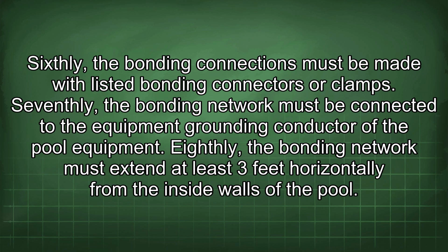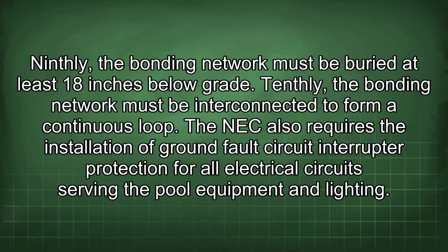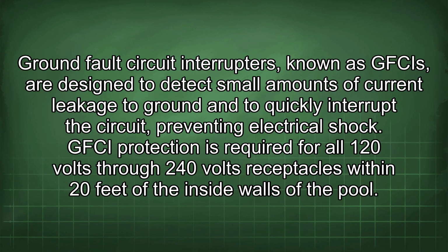Seventhly, the bonding network must be connected to the equipment grounding conductor of the pool equipment. Eighthly, the bonding network must extend at least 3 feet horizontally from the inside walls of the pool. Ninthly, the bonding network must be buried at least 18 inches below grade. Tenthly, the bonding network must be interconnected to form a continuous loop. The NEC also requires the installation of ground fault circuit interrupter protection for all electrical circuits serving the pool equipment and lighting. Ground fault circuit interrupters, known as GFCIs, are designed to detect small amounts of current leakage to ground and to quickly interrupt the circuit, preventing electrical shock.